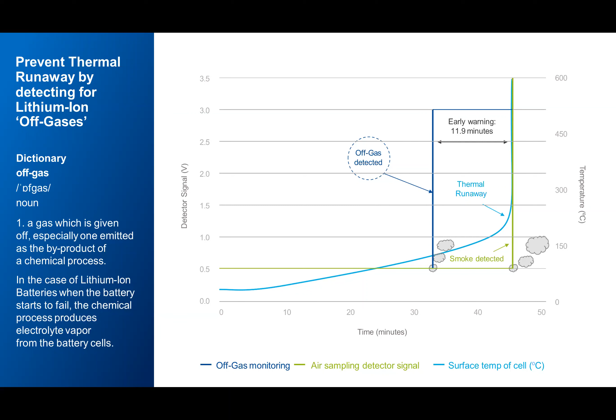So if we look at the point of off-gassing - the off-gas signal - in this battery cell, it was almost 12 minutes prior to actually hitting thermal runaway. That 12 minutes is what we like to call the golden time - the time we have to actually intervene, provide alarm and notification, activate systems that can remove the abuse stimulus, cool batteries, and allow personnel and others to get to safe locations.